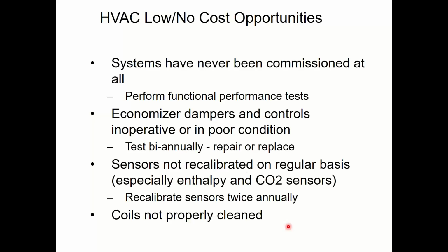The condenser coil, however, that's the coil on the outdoor airflow side of the equation. That doesn't have any major health risks associated with it being gross, although there could be stuff that flakes off in the air and goes like Legionella or something like that, but that's pretty rare. But that's going to reduce my heating and cooling capacity on my system. It is going to get a lot dirtier because there's really no way to filter that one. So cleaning the coils on the condenser side is probably like an annual thing for most buildings. It might be less or more depending on what's in your area. If you got like a crap load of cottonwood trees in your area, okay, it's going to be a frequent cleaning scenario. But it really depends on what's going on out there.